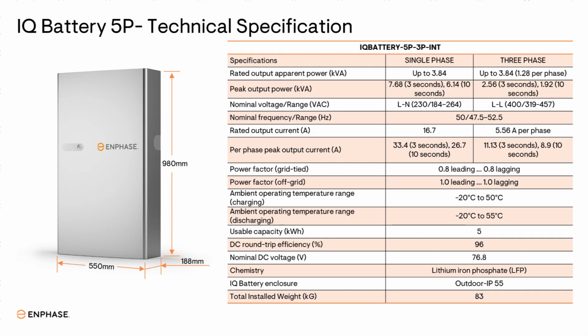We know the startup current is always 2 to 3 times higher than the rated current of that equipment, so these batteries can withstand those currents also. If you are operating any type of motor load with these batteries, you won't face any tripping or any type of issue there. For a single phase battery, it's 7.68 for 3 seconds and 6.14 for 10 seconds. And if you are using three phase batteries, it will be 11.13 for 3 seconds and 8.9 for 10 seconds.